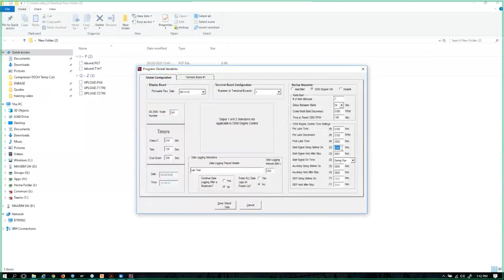Start signal delay before on. So generally, this again becomes my true prelube time. So in this case, I have 60 seconds. So what I'm doing is I'm going to prelube this compressor. So far, based on what I'm saying in my logic, I'm going to prelube this compressor for 60 seconds before I send the start signal to the engine.